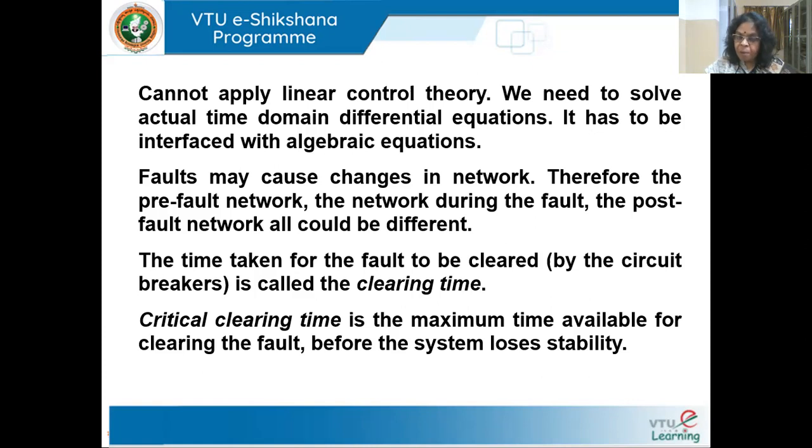Of course, if the fault remains, it's called a sustained fault. In most cases, sustained faults, if they're large, will drive the system to instability. Clear? Then I clear the fault. I have the post-fault network. The fault can be cleared maybe by opening a line, or the fault may clear naturally. If lightning strikes, it may clear by itself after some time. So that is a post-fault network.